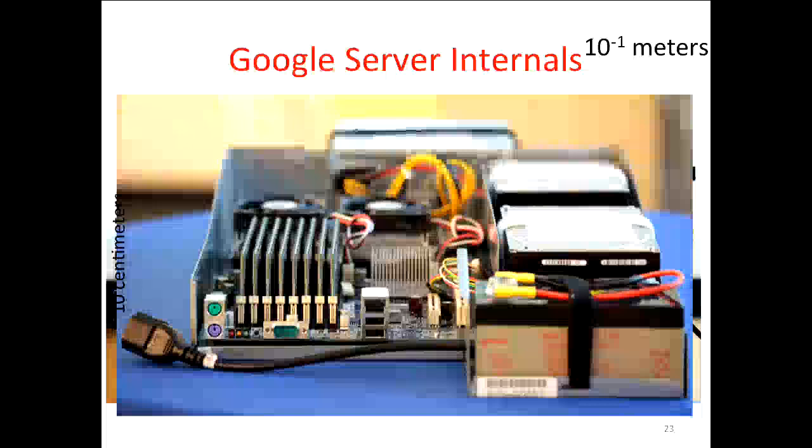And data centers have amazing power backups, right? Because they're 10 megawatt installations. They have to keep running, even if there's a power outage. So where do you get 10 megawatts of power from when the lights go out, when the mains goes out? Well, it turns out that these big data centers actually have several cascades of backup. So they have batteries for a very short period of time, and then they have massive diesel generators. And these things are about the length from here to that wall, and each one can generate a couple of megawatts of power.